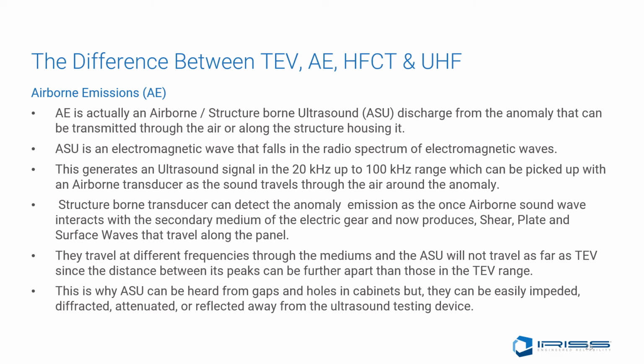Structure-borne transducers can detect the anomaly's emission as the once airborne sound interacts with the secondary medium of the electrical gear and now produces a shear, plate, and surface wave that travels along the panel. They travel at different frequencies through the mediums, and the ASU will not travel as far as the TEV, since the distance between its peaks can be further apart than those in the TEV range. This is why ASU can be heard through gaps and holes in the cabinets, but they can still be easily impeded, diffracted, attenuated, or reflected away from the ultrasound testing device.